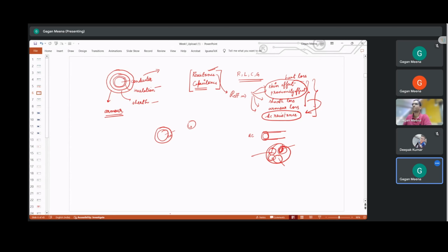Together they add up, and to reduce these sheath losses, what we try to do in transmission lines is make the impedances equal in all the phases, because we have mutual inductances between different phases, which would result in different inductances if we do the analysis. But to make them the same, what we try to do is use one important principle. Have you heard of transposition, Deepak?